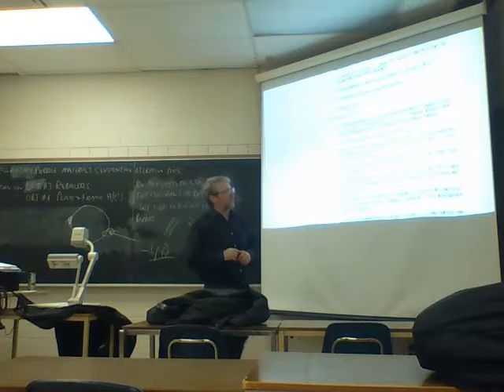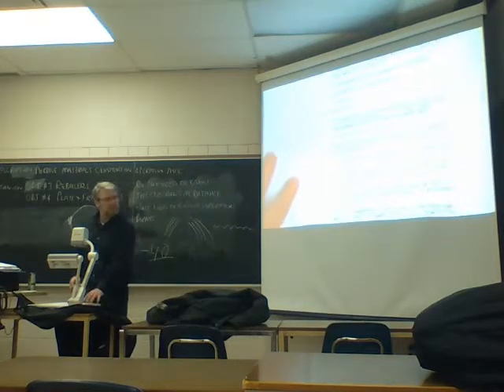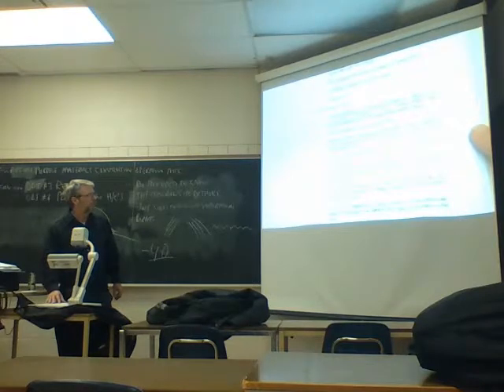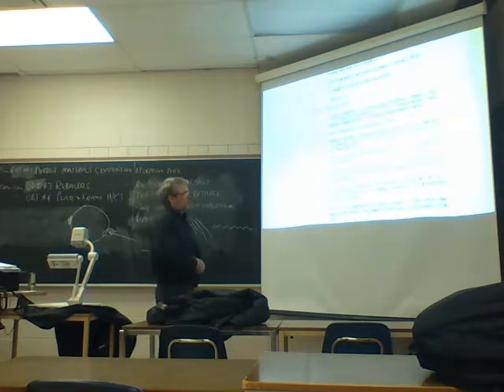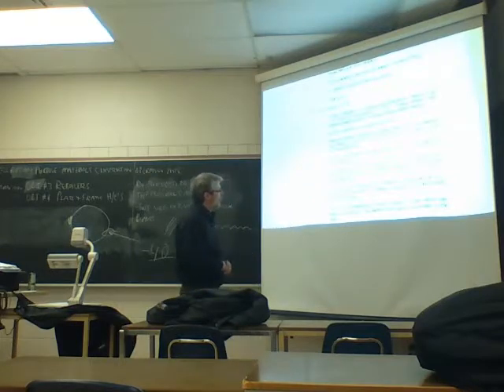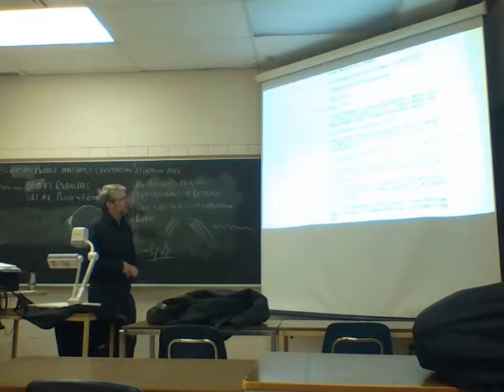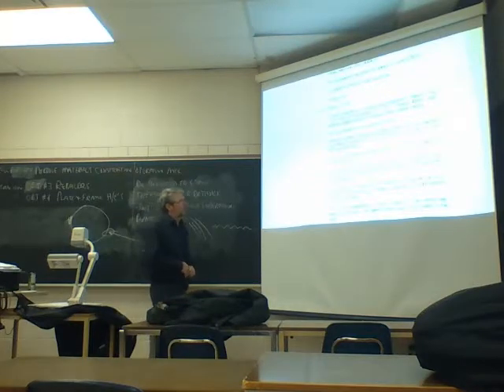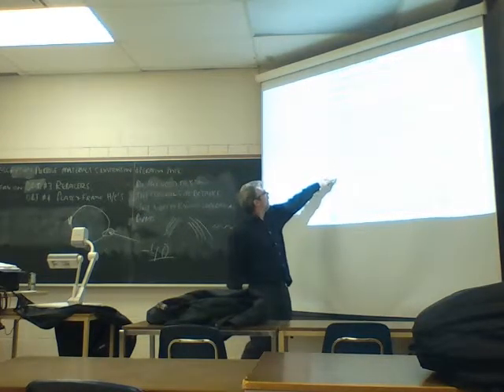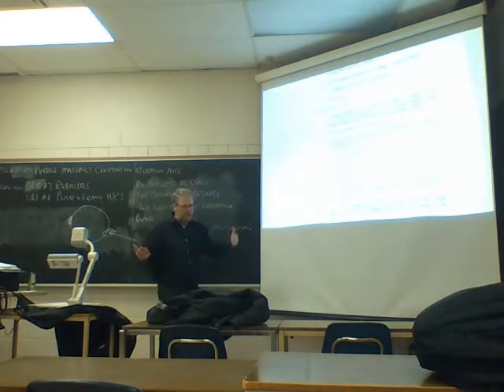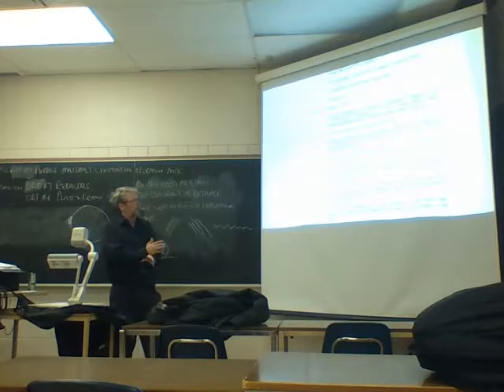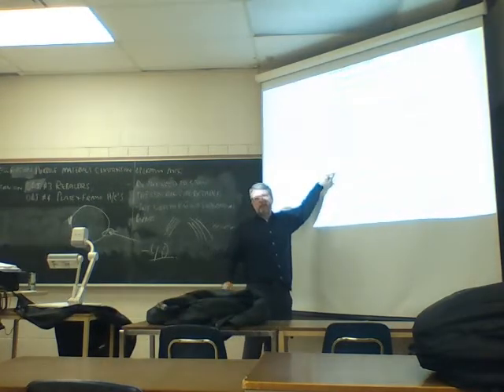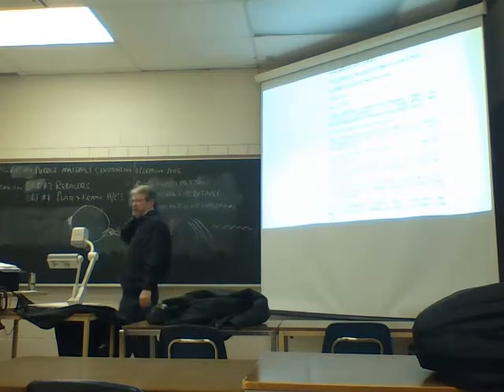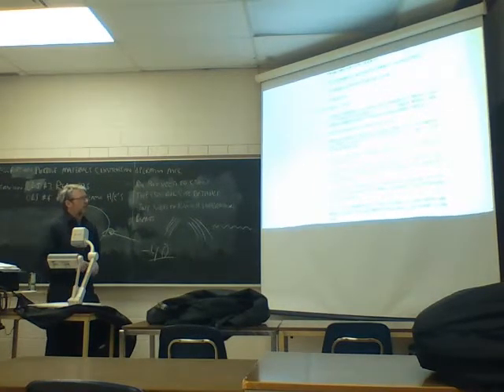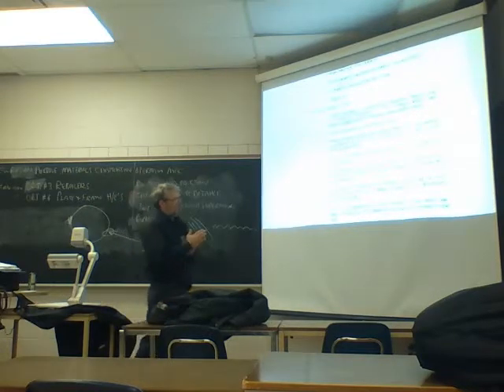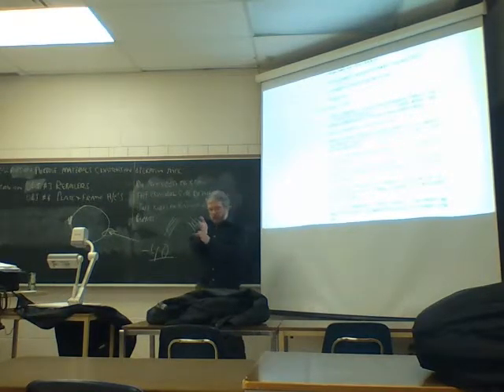Low flow rates creating velocities less than 0.1 meter per second can create flow distribution problems. This is the big one here - low flow rates, of course, you get very low flow rate, you're not going to get good heat transfer. This is the biggest one. There's a pressure drop across these units. That's one inherent problem, because you have very little space in between all those plates, you're obviously going to get pressure drop, more so than you will in the shell and tube heat exchanger.